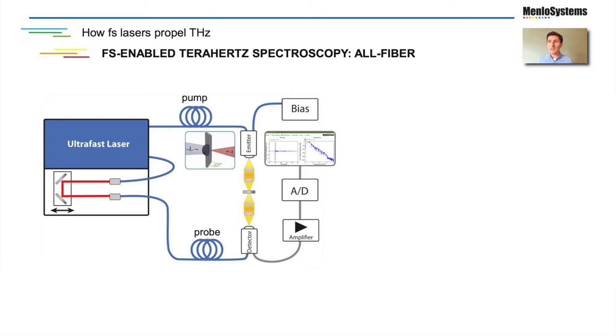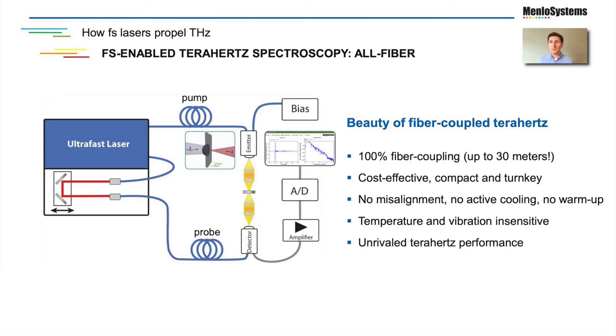This is the beauty of fiber-coupled terahertz: it is 100% fiber-coupled, the fibers can be as long as 30 meters, it is a cost-effective, compact, turnkey solution. It also means there's no misalignment, the system does not need to be actively cooled and does not need warm-up time, so it's immediately ready for operation. Finally, this leads to an unrivaled terahertz performance.